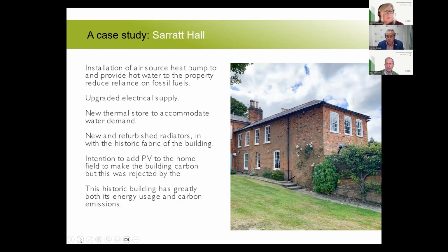We did a lot of modeling, with a lot of restrictions from the architect — not wanting to change the radiators, wanting to keep the old cast iron. So they had them taken to be cleaned out and repainted, which really drove us down the line of having to use 70-degree water.